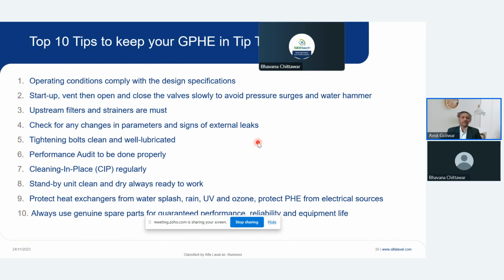Ensure that it is well lubricated and clean. There is no harm in conducting a performance audit on the heat exchangers which are already installed, because it may be possible that the heat exchangers you purchased at the time of project execution are probably running with a temperature approach of 5 degrees or 10 degrees. But now the same heat exchanger can be converted to even a 1 or 2 degrees approach.